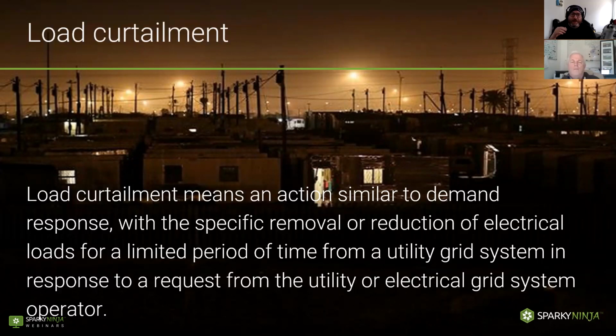There are two parts to this. There's load curtailment, and we also used to mention a term very early in the life of 722 called load shedding, which was like another step of this process. The idea being that when there are large periods of demand, fundamentally, there's not an infinite supply of electricity. We should know that as electricians. When we put too much demand on, the grid is going to suffer. So there need to be arrangements in place to allow us to dampen down our demands to allow the grid to cope with that excess demand in other areas, maybe even geographically. So this technology will have that setup implemented, and that takes a lot of the work out for electricians, because we don't really have to quantify it if it's set up to do that. Technically the grid can also communicate with the charger to say, okay, you can have more, and then it can die down when needed.